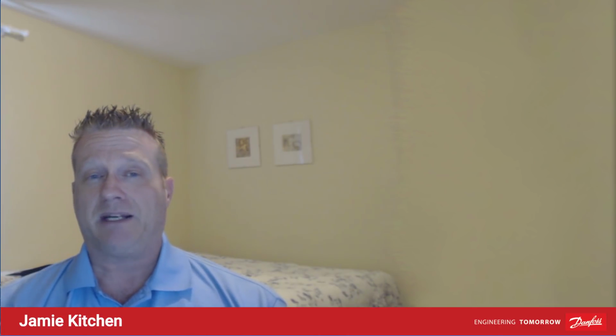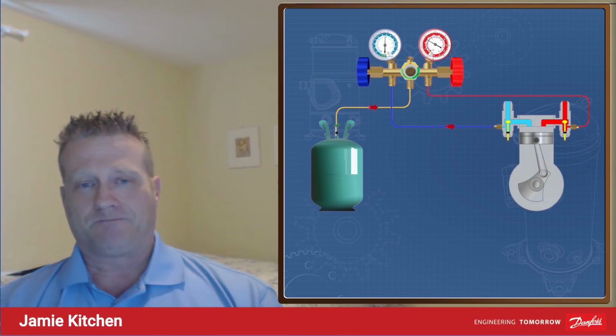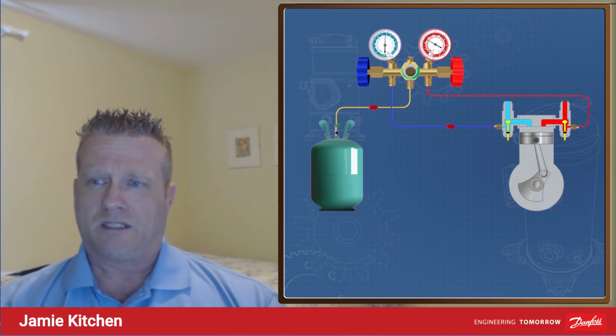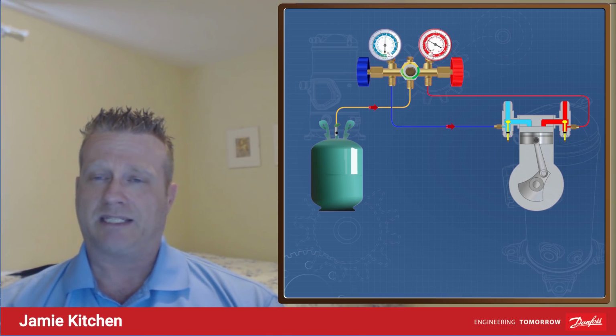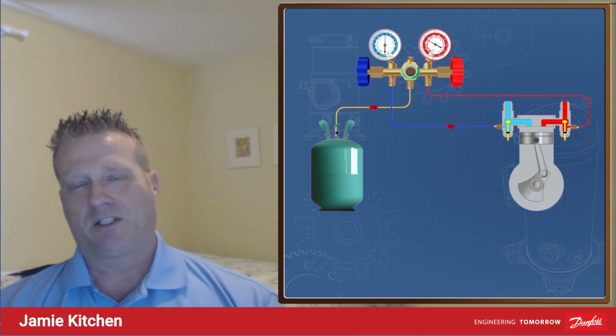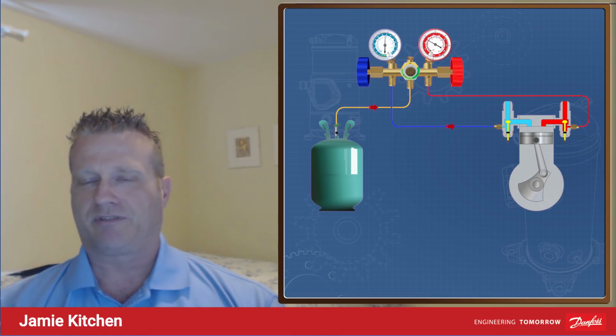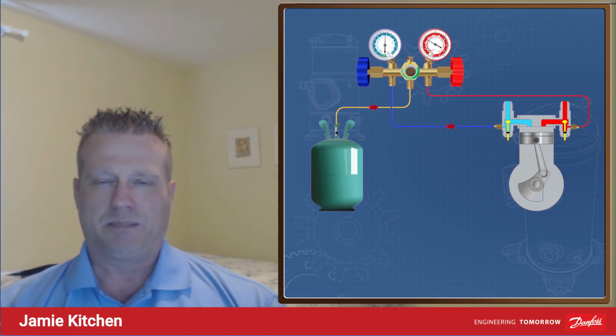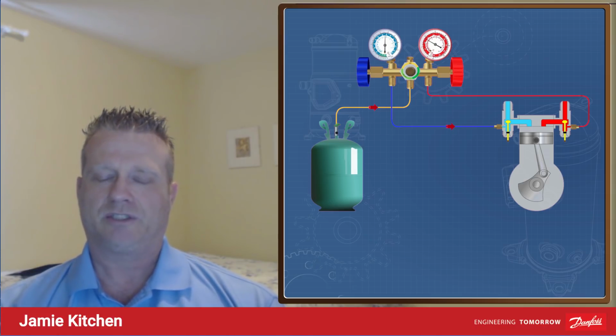The next thing you want to look at, if everything checks out in the compressor, you've checked your voltages and your current draw, and that checks out fine, great. You've eliminated a big cause of failures. The next thing you want to do, of course, and we might as well start with it now, is charging. When you charge a system, and I shouldn't even have to talk about this, I know a lot of people are probably going to roll their eyes, and that would be great, except for one thing. According to some stats I looked at, almost half the units that are out there are overcharged. And when you consider the push for efficiency these days, people are paying for SEER 18 systems. You're not going to get SEER 18 out of that if the system isn't charged properly. It's a huge issue.